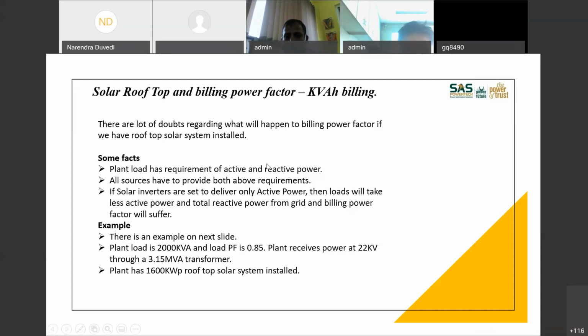Both these powers ultimately you have to draw from some source. When you don't have a solar rooftop, you draw everything from the grid and your local reactive power capacitors. If you have solar, you start drawing less active power from the grid, and the entire reactive power from all other sources. So that's the reason there could be some change. So I have created some simulations, so we'll understand it better when we go to the next slides. If solar inverters are set to deliver only active power, then loads will take less active power and total reactive power from the grid, and billing power factor will suffer.